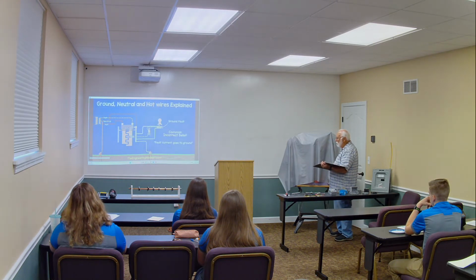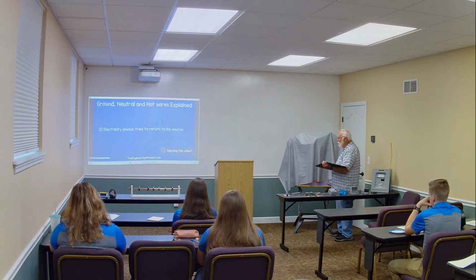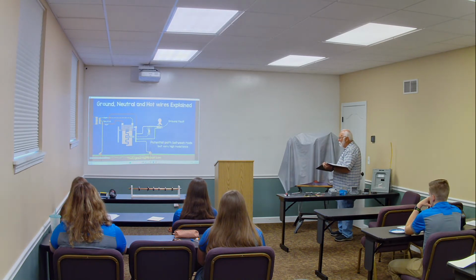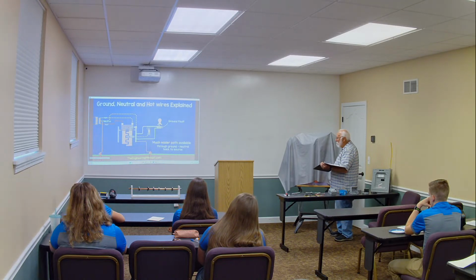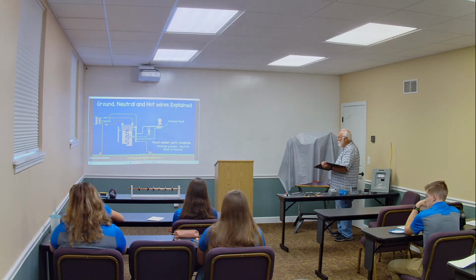Many people think that during a ground fault, electricity flows through the ground rod and into the earth. But remember, electricity tries to get back to its source, not just into the earth. Since there's a ground rod at the transformer, there is a potential path for the electricity to get back to the source, but this path has very high resistance or impedance. Electricity takes preference for the path with least resistance, so since we already have a low resistance ground wire providing a direct path back to the source, the ground fault will take this route instead.